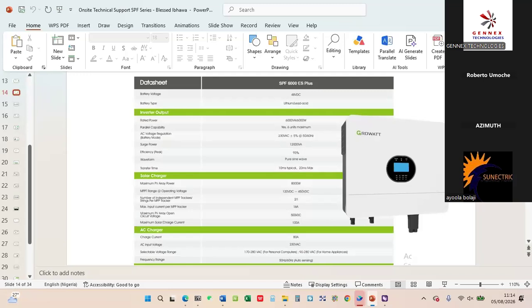So for that question, I'll answer like Growatt - this is Growatt's position. If you are connecting above the rated power, you need to consider where your panels are relative to the inverter - how much power do you think you'll lose before it gets there. That's one consideration. Then secondly, are we dealing more with voltage or current? Because the machine is more susceptible to voltage.